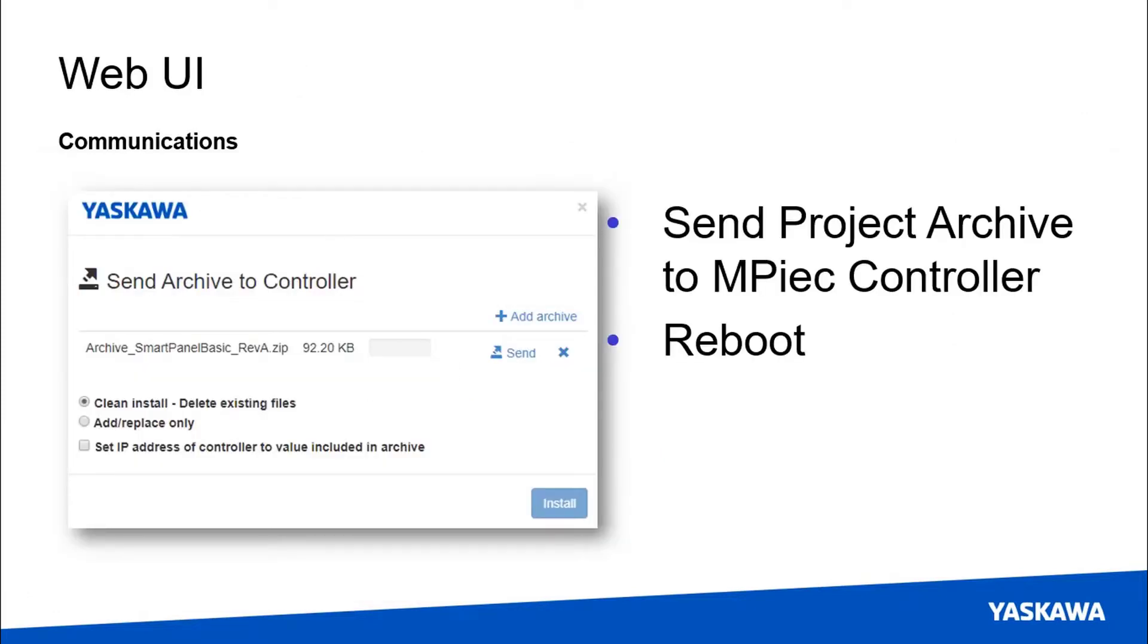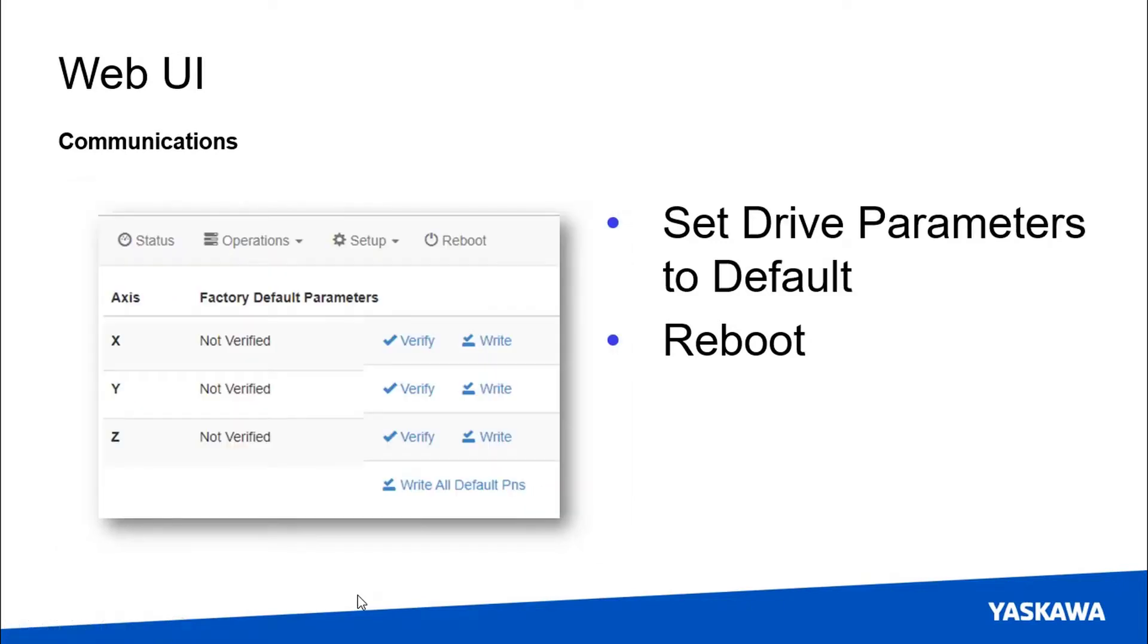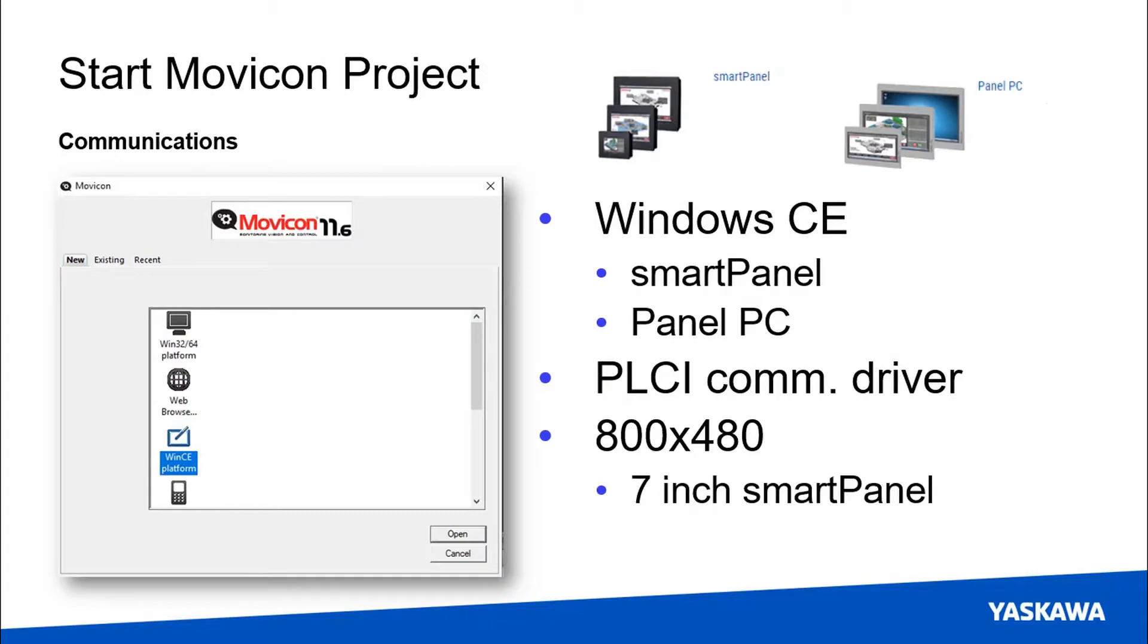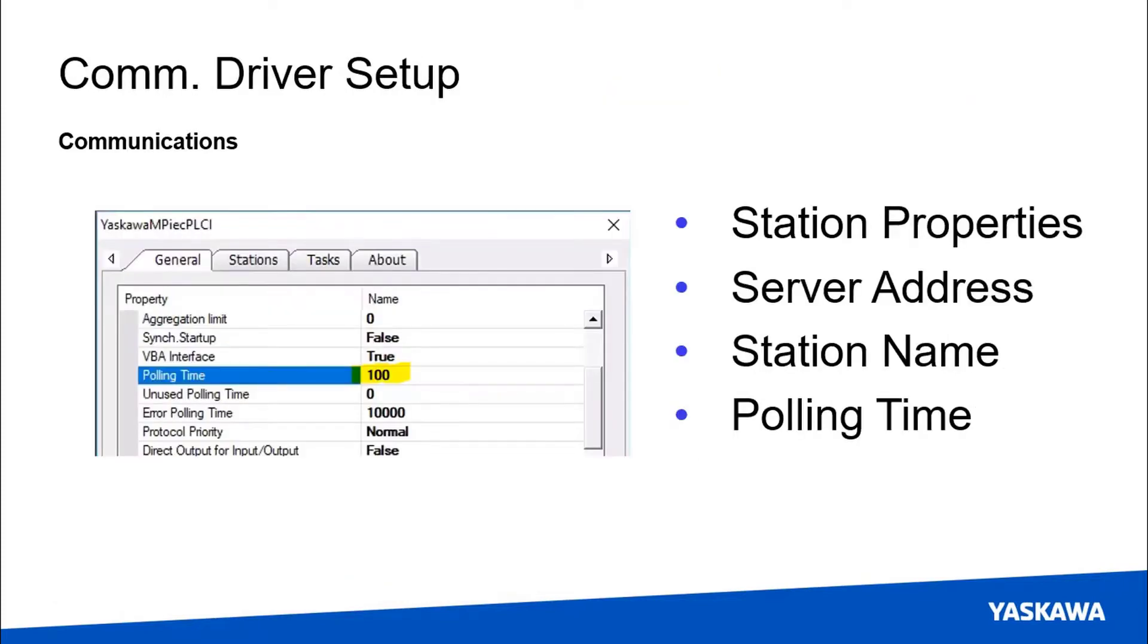You've seen the web UI before to send the project archive and we'll have you set those drive parameters to default just to be sure. When you start that new Movicon project it'll be again in Windows CE with that same dimension 800 by 480 for the 7 inch smart panel. This time we will have you do a tweak to the polling time of the PLCI driver and set that to 100 milliseconds update interval.